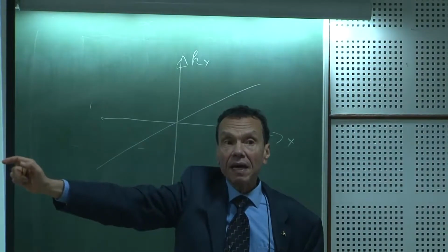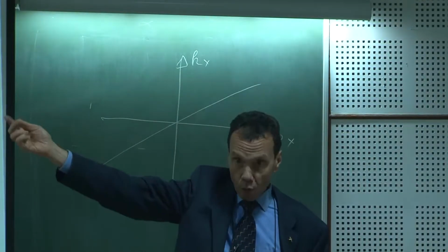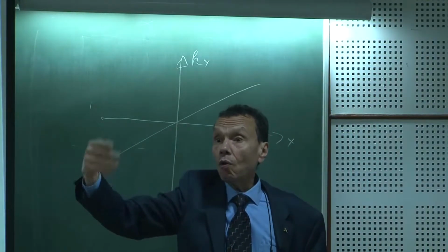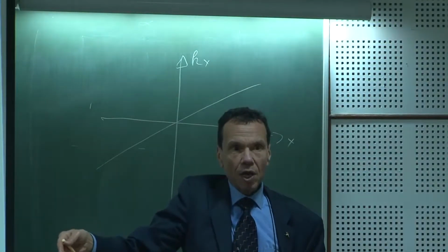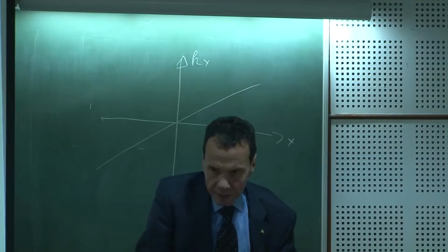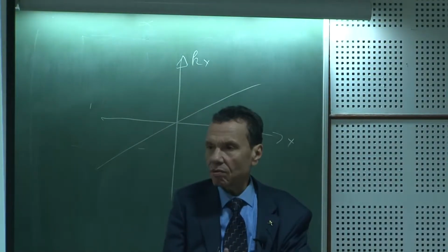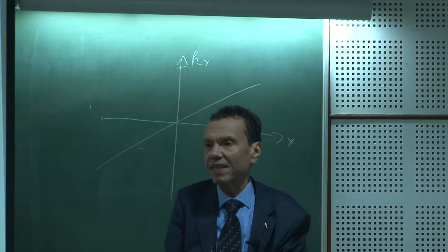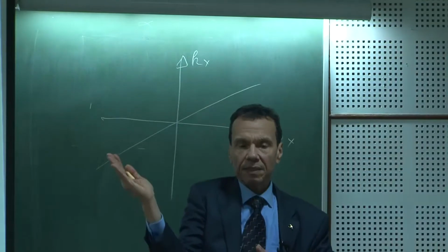Now you may apply the x ramp for a longer time. You will have more or stronger ramp for the same time. Usually the time slots are fixed because you have a patient who moves and so on, so you don't want to play with the time. So in this case, you will play with the ramps.